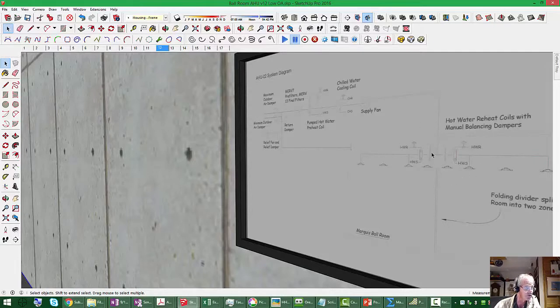In other words, there's nothing to vary the volume. It's a reheat system. It's got an economizer, it's got a preheat coil, and it's got a chilled water coil. So there's the answer to the first question. It's a constant volume reheat system. And right there is an opportunity. Okay? And I'll leave you to ponder that. We'll actually come back and talk about that in a different webinar.